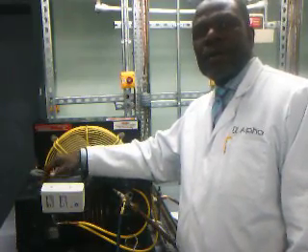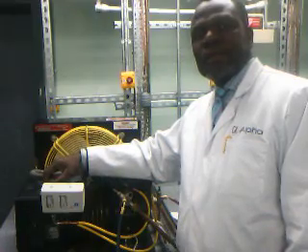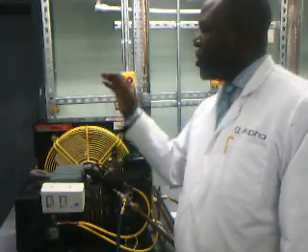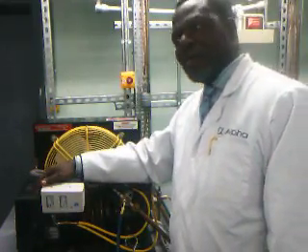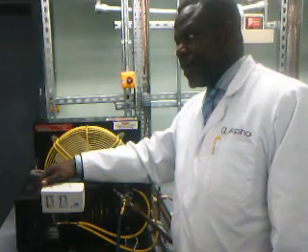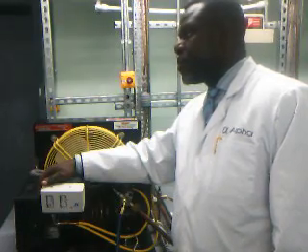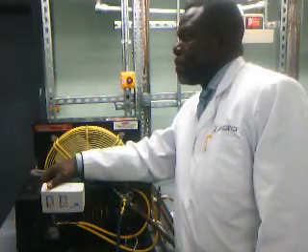Is this the most accurate way to determine whether you've got the right size condenser or not? It is the most accurate way of knowing that the condenser you've got is matching the evaporator and the compressor. So that means that you could come to a machine and the condenser could be the wrong size. Exactly, it could be.